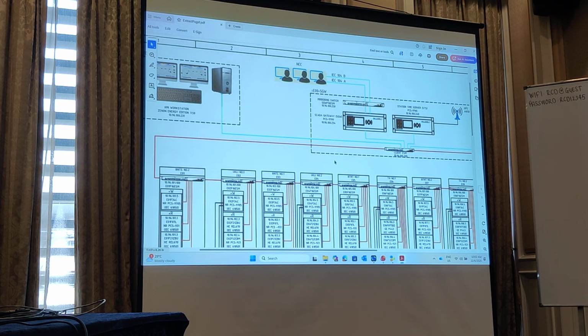Okay, so goose works more like a signal transmitter. They transmit and they receive, but MMS is more like a record, like an event recorder. Whatever happened, it is sent as information to the client. But goose is not only sending information, it is something like triggering the thing to happen. You understand, like a tripping logic. Tripping logic, you want the tripping to happen. The goose is the reason it's happening. So it's a trigger. It's a triggering point.